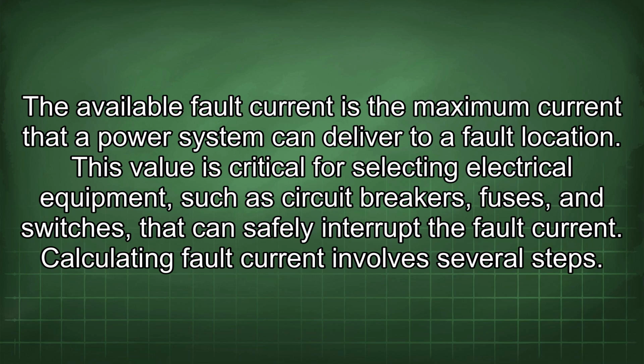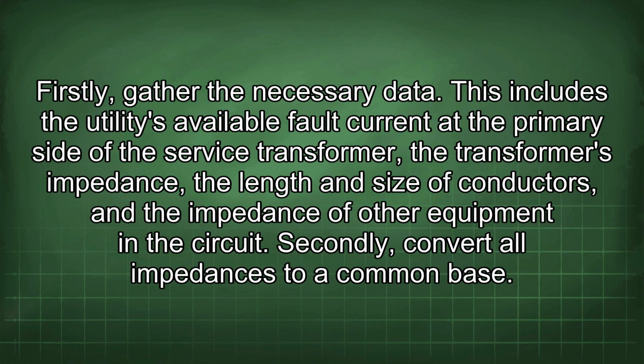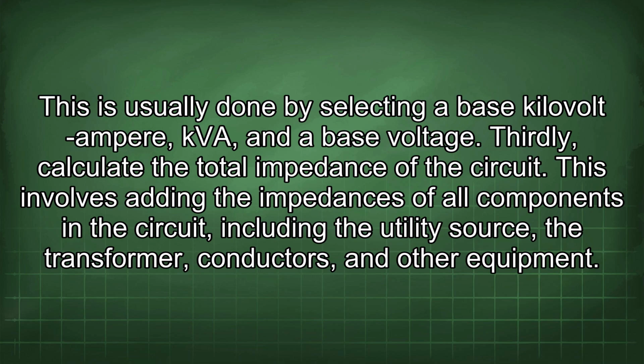Calculating fault current involves several steps. Firstly, gather the necessary data. This includes the utility's available fault current at the primary side of the service transformer, the transformer's impedance, the length and size of conductors, and the impedance of other equipment in the circuit. Secondly, convert all impedances to a common base. This is usually done by selecting a base kilovolt-ampere, kVA, and a base voltage.